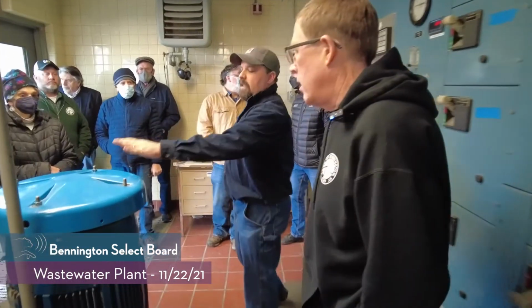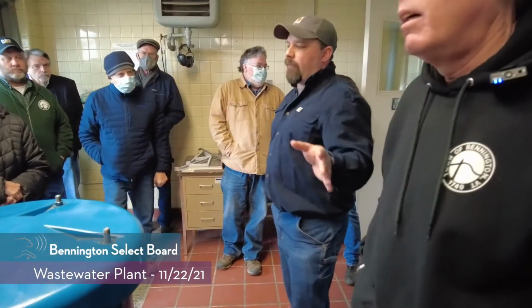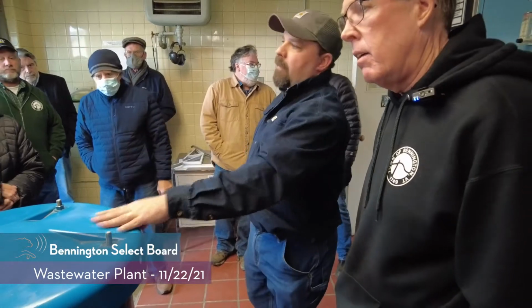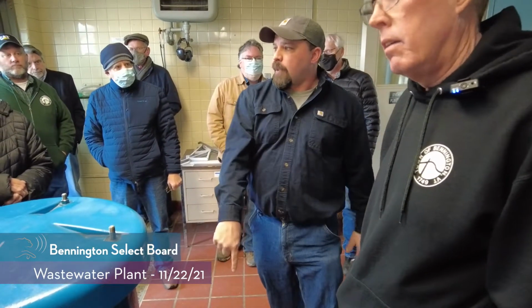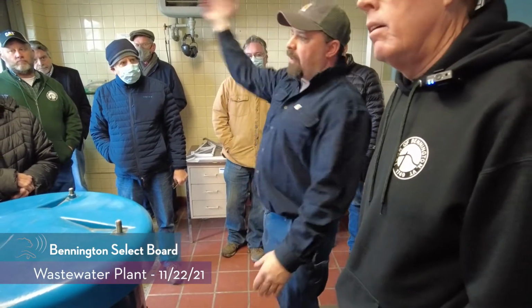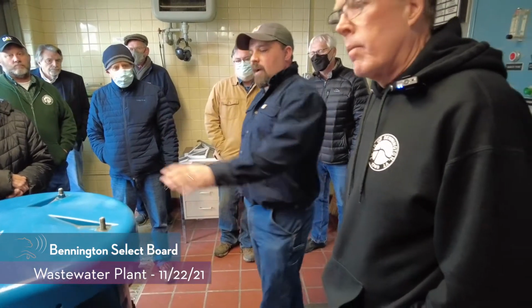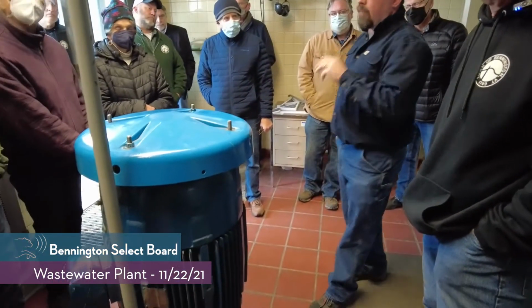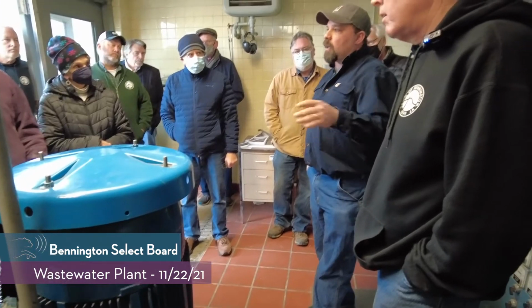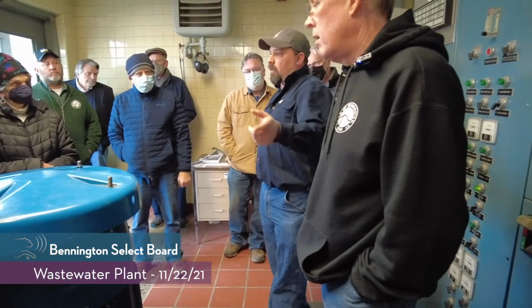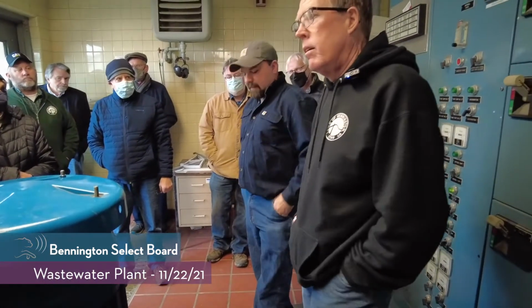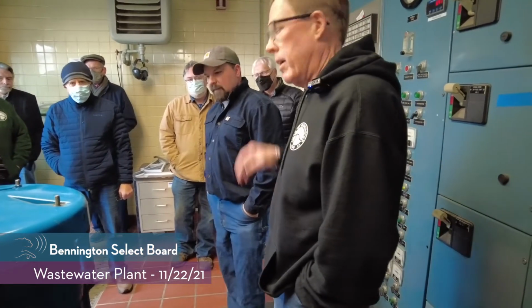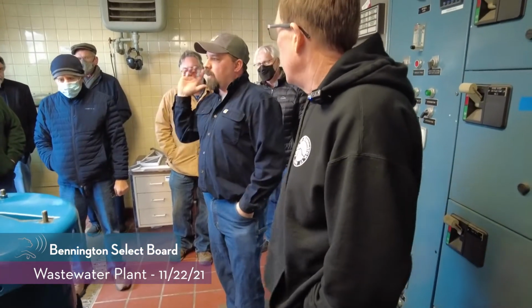So these 4 pumps are the only pumps that pump all the flow. Without these pumps, this can't happen. It takes it from 3 stories down and pumps it up there, and the rest is gravity through the plant. These are 50 horsepower motors. There's 4 of them. Normally only 1 or 2 are running at a time. Every once in a while, during like Irene, the 3rd will kick on, but never 4. 4 is too much, it will overflow.